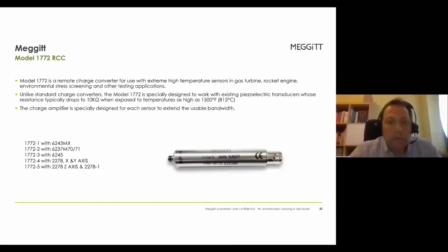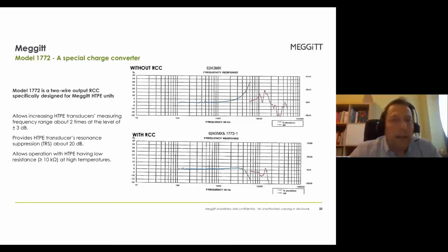If you want to see a plot, here it is. On the top part of the slide you have the classical 6243M unit, which is not using the remote charge converter. Here the resonance frequency is clearly visible, and the usable frequency with about 5% deviation is around 3 kilohertz. Instead, with the RCC in use, we have suppression of about 20 dB, and the -5% deviation point is at around 6 kilohertz, almost doubling the usable frequency of the unit. It's quite interesting.